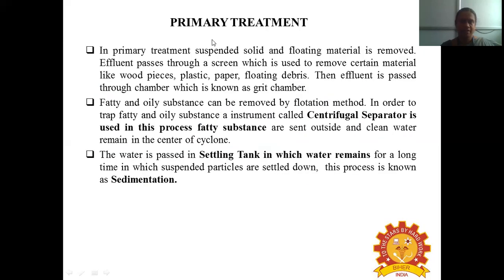In primary treatment, suspended solids and floating materials are removed. The effluent passes through a screen where materials like wooden pieces, plastic, paper, and floating debris are removed. Then the effluent passes through the grit chamber. Fatty and oily substances can be removed by the flotation method, using a centrifugal separator. The fatty substances are sent outside and the clean water remains in the center of the cyclone, which is an integral part of the centrifugal separator.